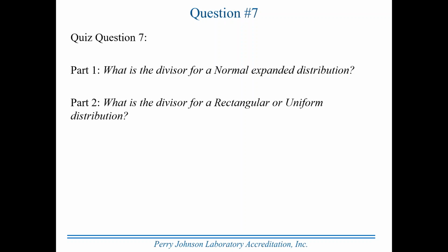All right, let's talk about part 1 for a moment. The divisor for a normal expanded distribution is K. Now we get the normal expanded distribution off the calibration certificate. We also get the coverage factor from that. And in most cases, K is going to be equal to 2. So you would take the normal expanded distribution divided by 2 to arrive at the standard deviation, or the standard uncertainty. Now, what's the divisor for rectangular or uniform distribution?